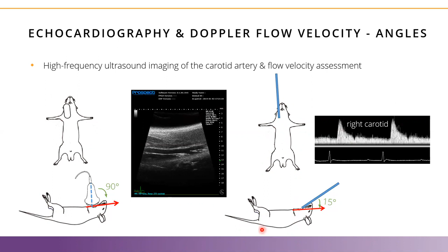However, to do a flow velocity measurement, you would prefer to do it at as sharp an angle as possible. And I will explain in a little bit why that is the case. Here you can see a Doppler flow velocity probe showing you the wave spectrograph of the flow velocity in the right carotid artery. And here is the indication of the angle of the measurement.